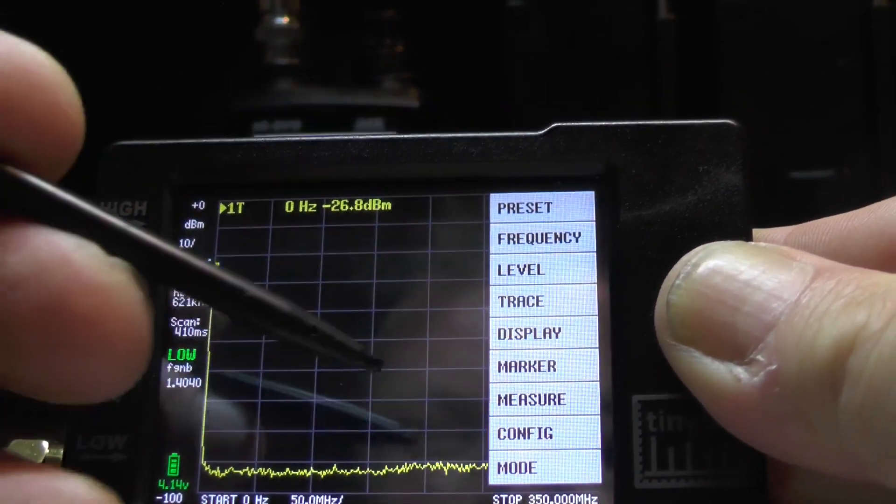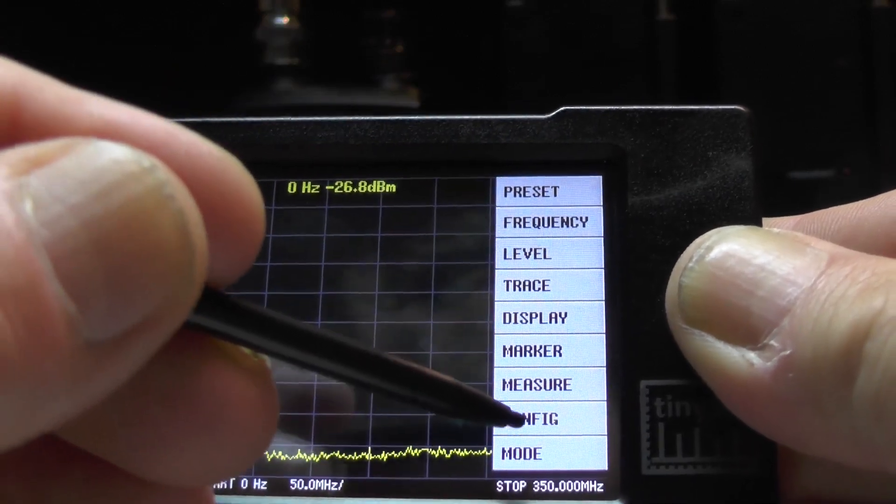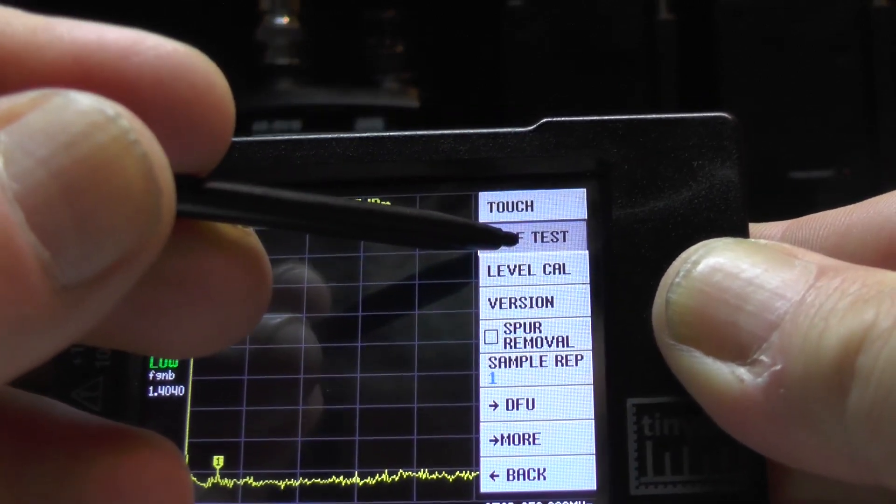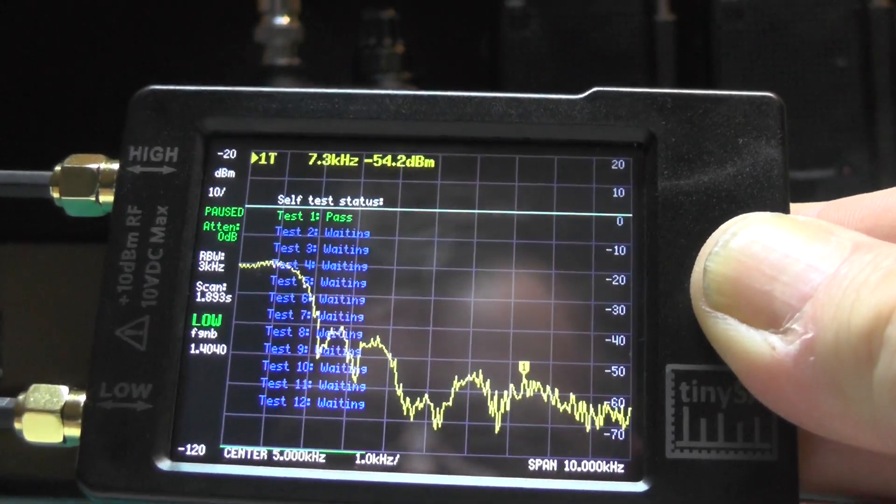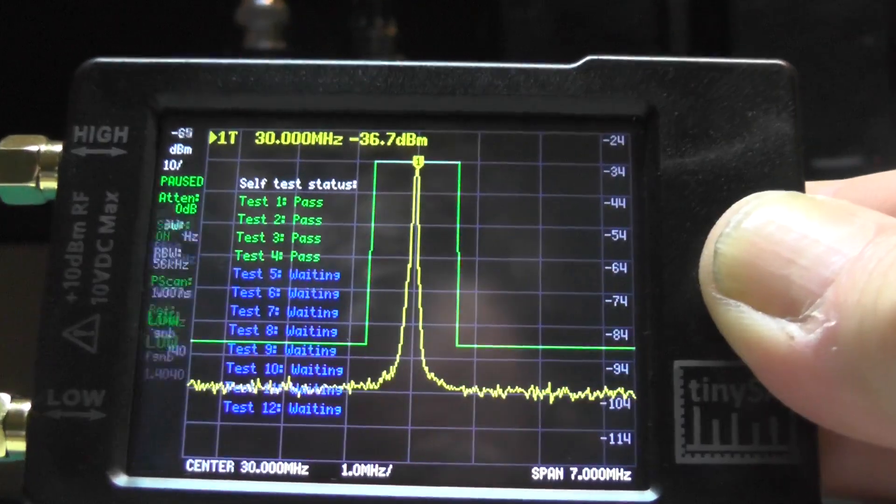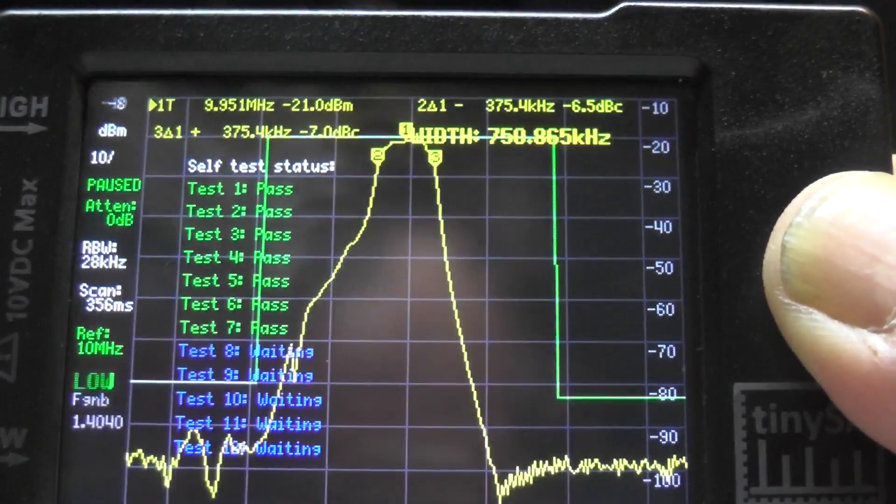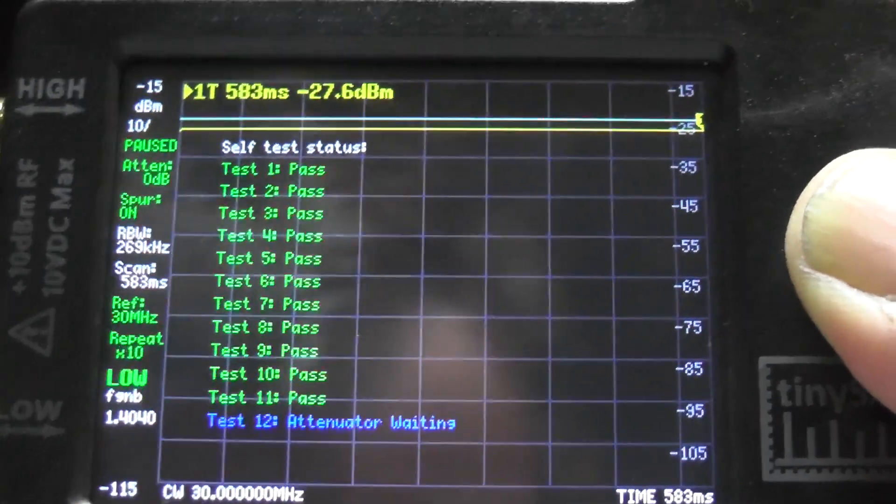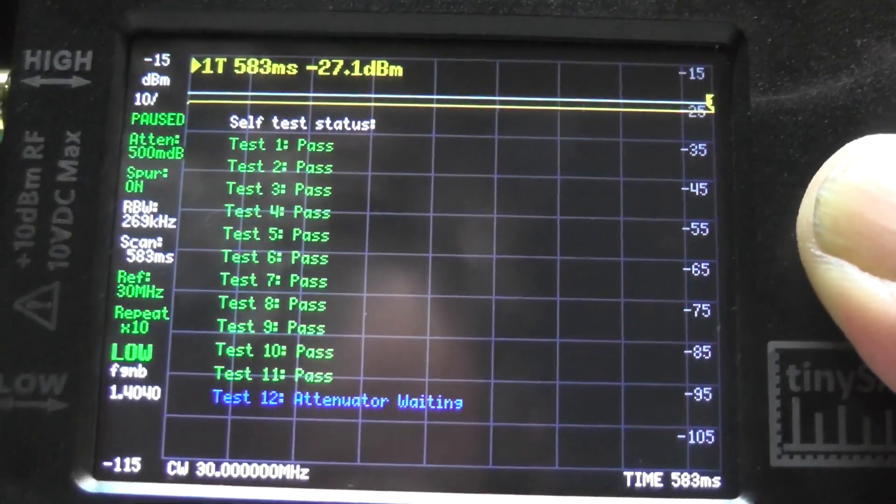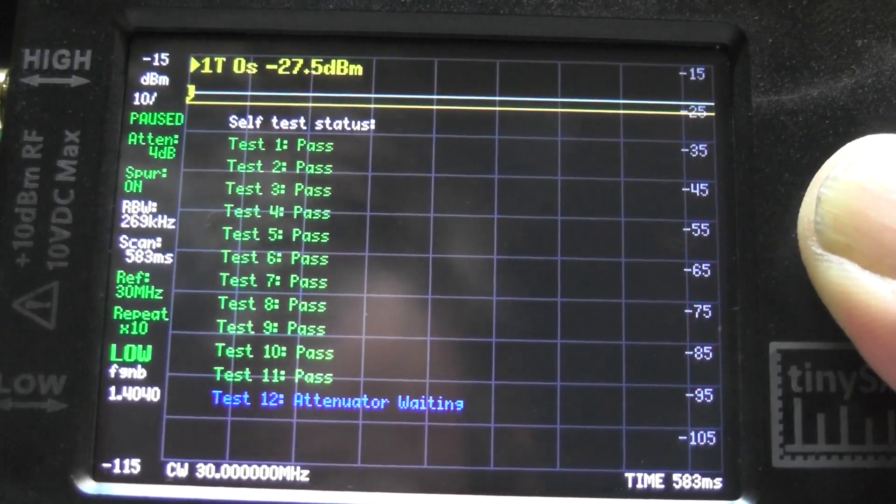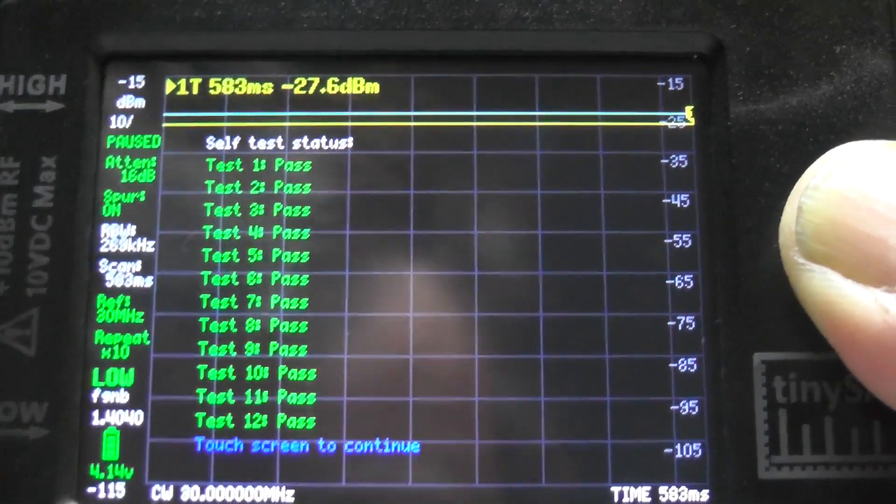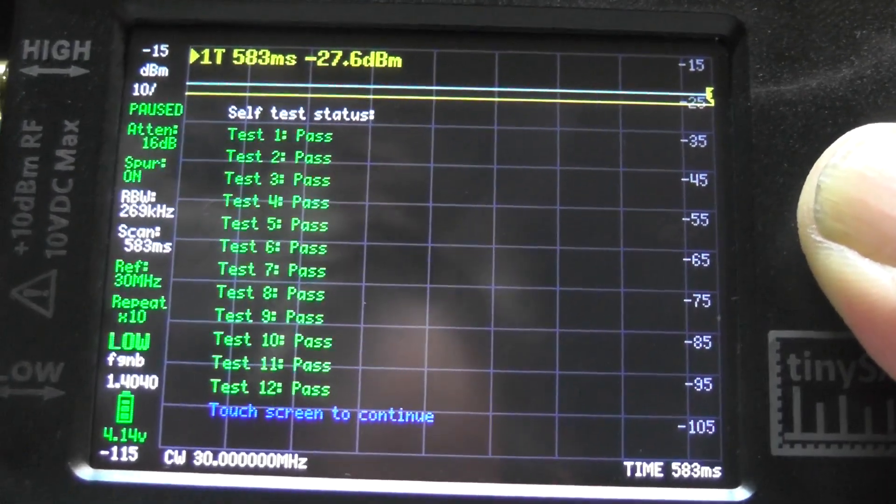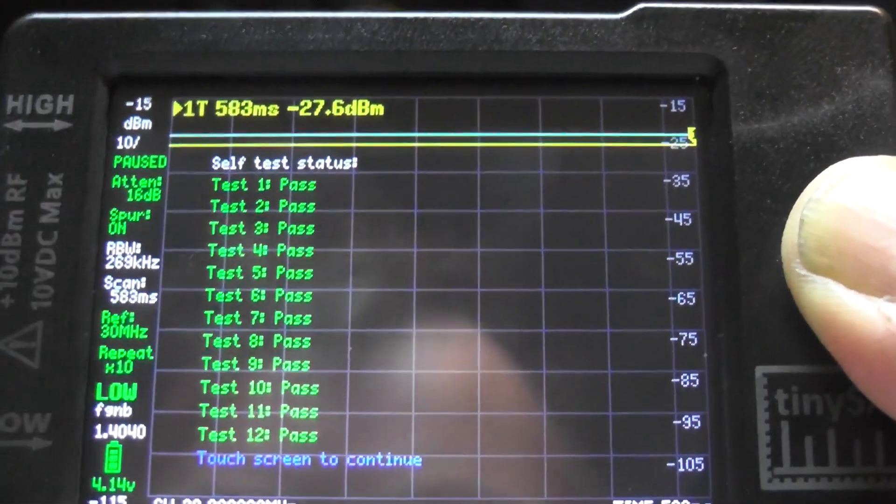Just press on config at the bottom here and click on self test. That's going to run through its self test. It should pass them all. Oh that was a nice pattern. Now test number 12, it says attenuator waiting. Lovely, it's passed the self test. It says touch screen to continue.